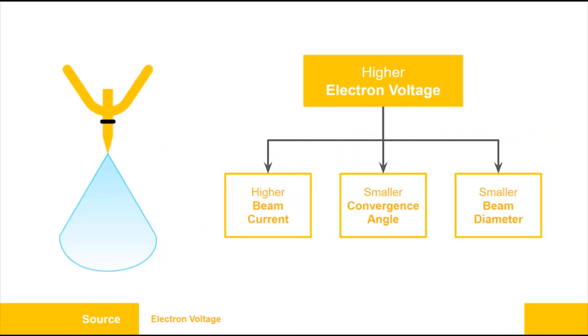The source is possibly the most important, as it is the source of the electrons themselves. The main parameter that you as a user can control is the accelerating voltage of the electrons. Higher voltages will result in a higher number of electrons, a higher current, because you are extracting more electrons at a higher rate from the filament. You will also have a smaller convergence angle since the electrons will be more directed towards that potential. Similarly, you will have a smaller beam diameter because of the directedness of the beam.